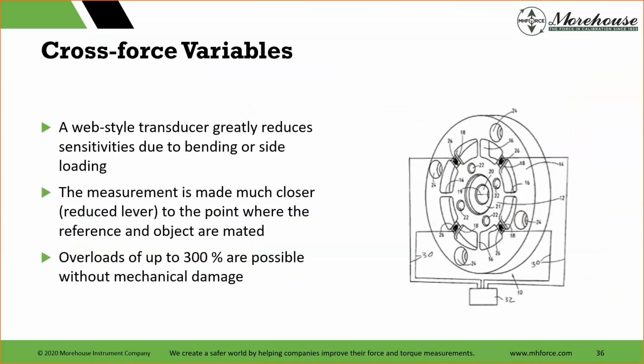The measurement is made much closer, with reduced lever to the point where the reference and object are mated. With this type of design, the Stahlwille cells are very good load cells, very good torsion cells. Overloads up to 300% are possible without mechanical damage. The other interesting thing Stahlwille does is it has a chip. It records exactly the life cycle of the cell. Say you have a 300 Newton meter cell. It'll record that it was taken to 330 Newton meters 3 days ago. It'll record if your technician took that to 600 Newton meters. You can go back and pull the log and say, this cell was taken.